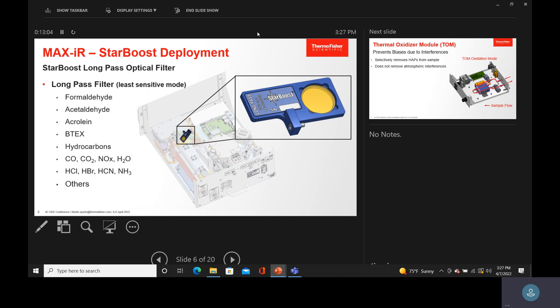This is what the filter looks like in the system — here's the actual spectrometer, here's the IR source, a five-dollar glow bar compared to a very expensive laser. Here's the gas cell: light goes in, comes out, goes up through the filter, then into the gas cell — 48 bounces for a 10-meter path — and onto the detector. This detector can be switched between DTGS and MCT; you just pop it up and snap it in. There's no alignment for anything. Everything is pin-mounted, and the two turning mirrors are fixed — there's no adjustment on this system whatsoever.